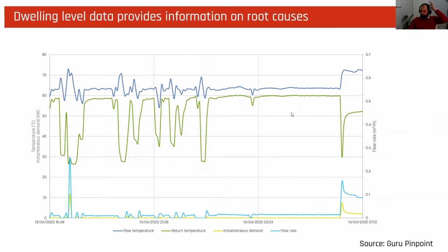And here's a quick example of the type of data that we'd be looking at. This is from a single dwelling, and the dark blue line shows the network flow temperature, and the dark green line shows the primary return temperature. Effectively what it's showing here is an example of an HIU that's performing poorly. The flow and return temperatures are very close, which shows the unit's not working particularly well, and there's an issue with that unit. So this would be a good example of where we want to go into that dwelling and look at how that HIU is performing. Is there something different in the way it's performing compared to other HIUs? Through that gathering of knowledge, we can then propose interventions to roll out across the site.